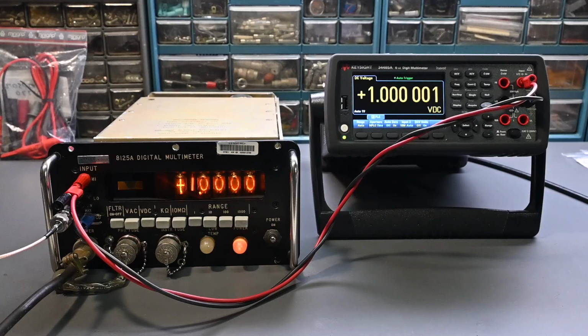So when you're doing the calibration and you reach through from the bottom, there are little holes, and that's how you get to the potentiometers for the calibration. When you reach through those holes, you have to use an insulated screwdriver because you wouldn't want to short out that bottom shield. Now, there's also a panel on the bottom of the instrument that holds the power resistors for heating the instrument in very cold weather, but that metal panel is not electrically floating because it's tied to the front panel.